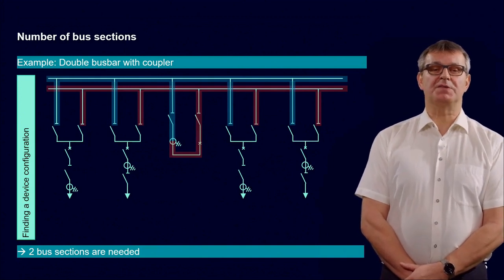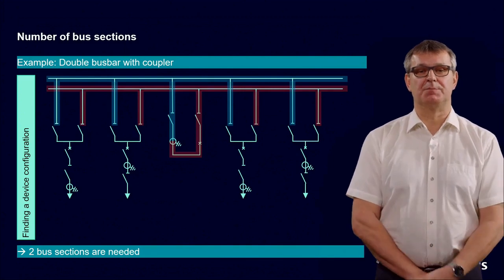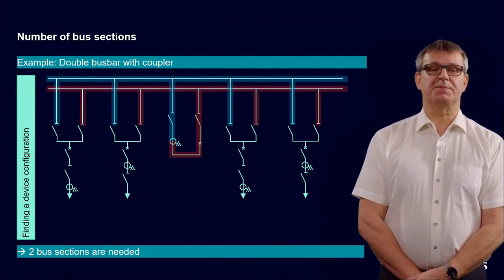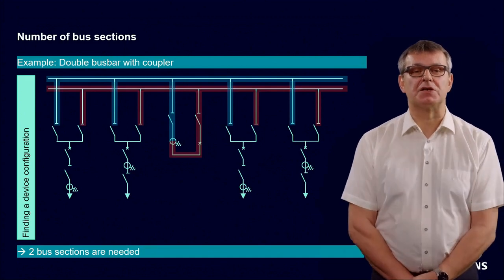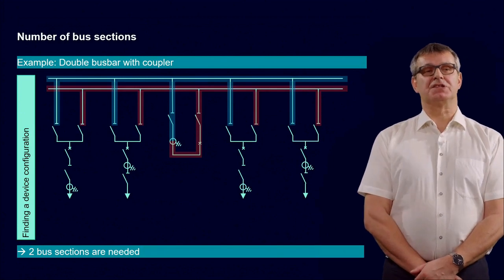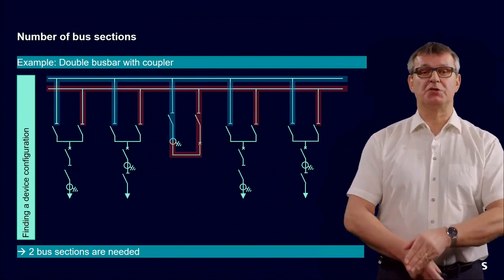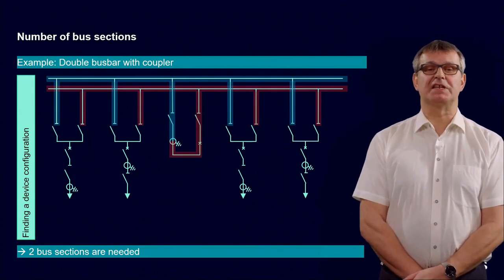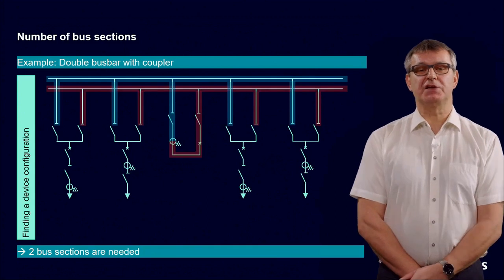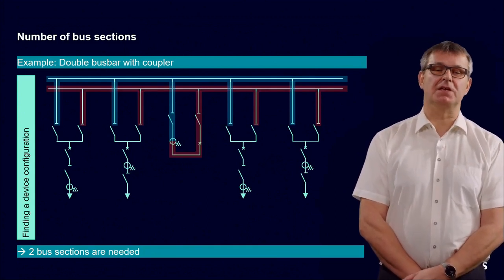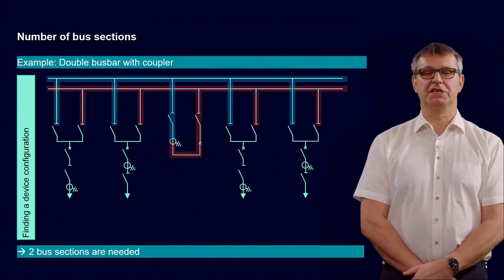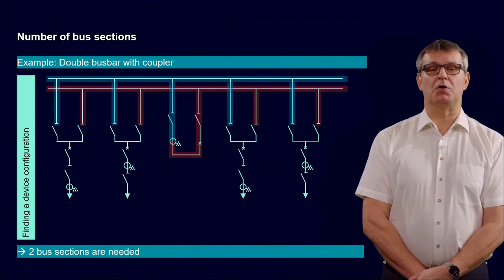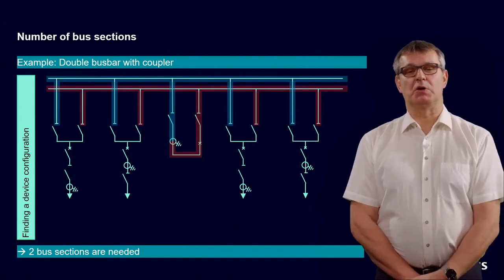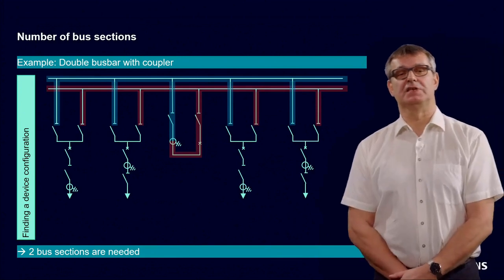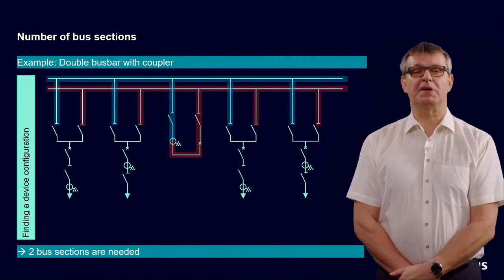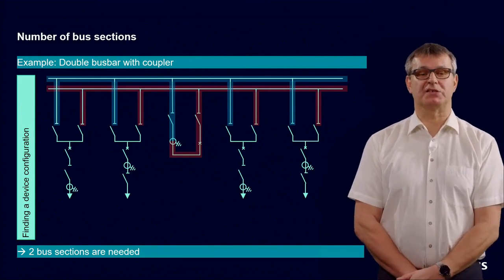You can see here we have the double bus bar. Here's bus bar 1, bus bar A, colored in blue. And bus bar B, or bus bar 2, is colored in red, I guess. As it is a differential protection, the split between bus bar A and bus bar B will be done in the coupler, exactly at the current transformer. Here you can also see an example of a coupler with only 1 CT. 2 CTs would also be possible, but here we have an example with 1 CT only. So, how many bus sections do we need in our example? We need 2 bus sections.